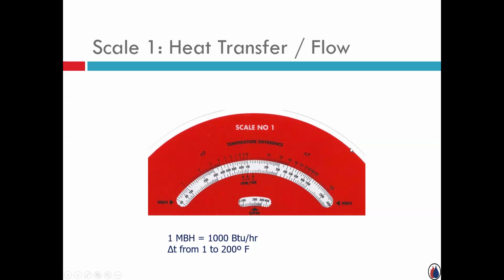Jumping right in, scale one. Scale one just talks about the relationship that exists between BTUs, heat transfer, and flow rate. And as we discussed last week when we start looking at pumps and pump curves, flow rate is typically described in gallons per minute. The scale is made up of this big white band, and inside there is listed BTUs, the load, BTUs per hour, MBH. So it's really thousands of BTUs per hour.